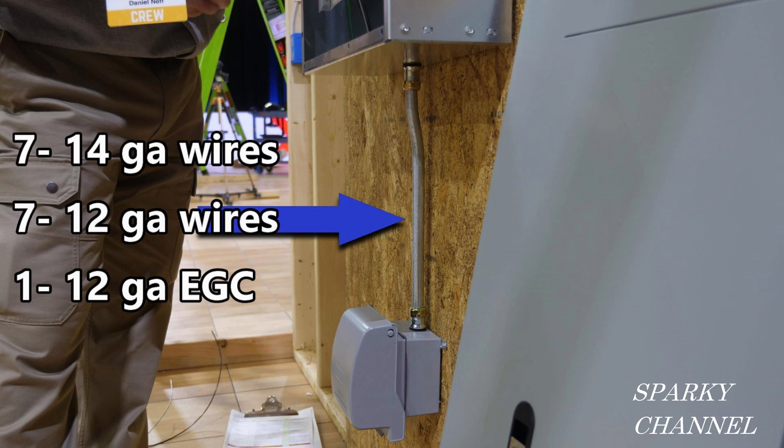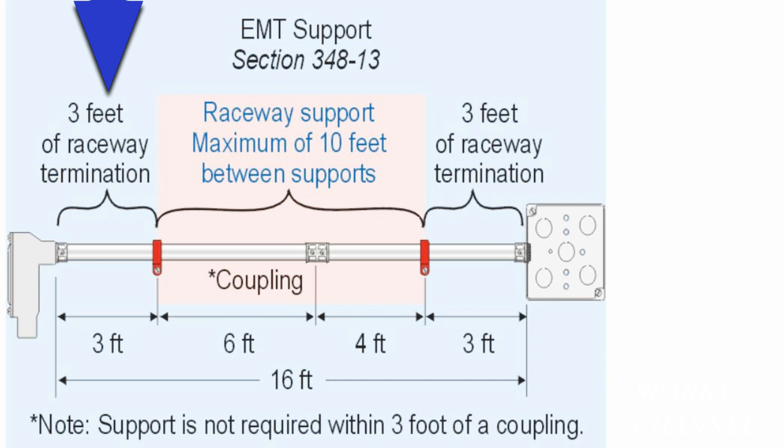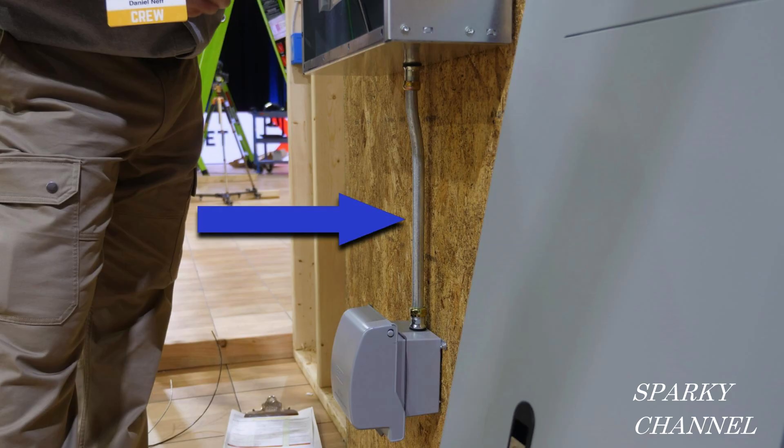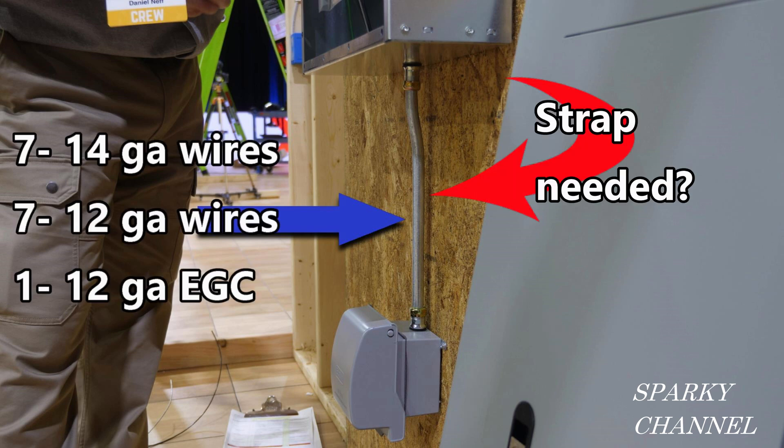Now let's check out and see if this piece of conduit needs a strap. Let's see if it needs to be strapped to that wall. Here's a graphic depiction of the code showing that a strap needs to be installed within three feet of raceway termination. Since our EMT is only 22 inches long, it does not need a strap. Let me know how you did in the comments section below.